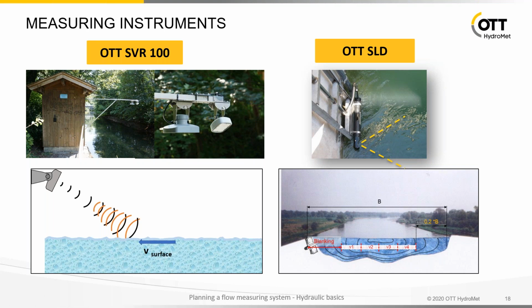You will get the velocity along the acoustic beam, and if you know the geometry of your sensor head, you will have an X component, which is in flow direction, and the Y component, which is pointed to the wall. So Y is usually 0 and the X component is used for discharge computation. You can set up cells. With the SLD, you always have 9 cells. From our experience in the field, it makes sense to have bigger cells and just to work with 4 cell velocities. This is the sample volume, finally, which you can then use for doing the velocity index discharge computation.